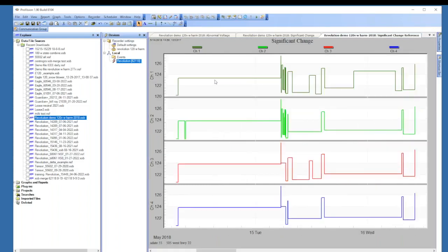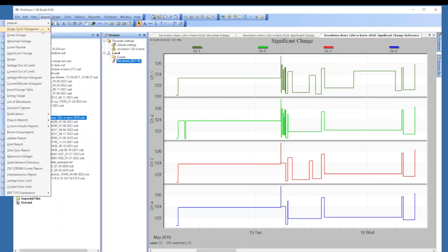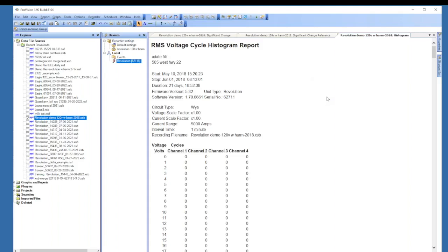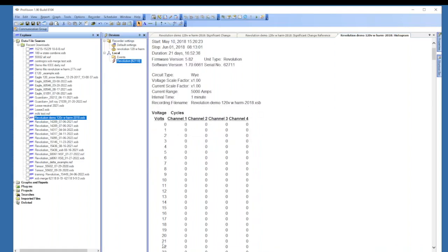And you can zoom in on these and look at those closer. One of the other reports, especially if you're looking for flicker or high voltage or even loose neutral: if you go into the report and single cycle histogram, there is an RMS voltage. Now the recorder collects all the raw cycles, voltage cycles and current cycles, and puts them into a bucket. So in voltage, it's the closest bucket. So in that first column, we have our voltages, and they do round up and down.